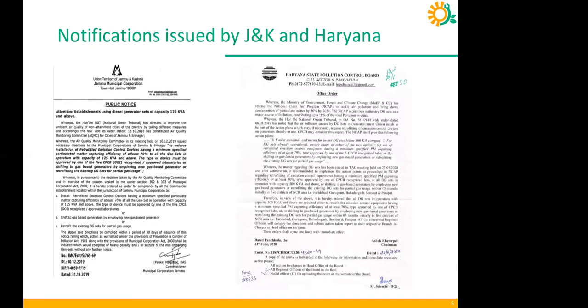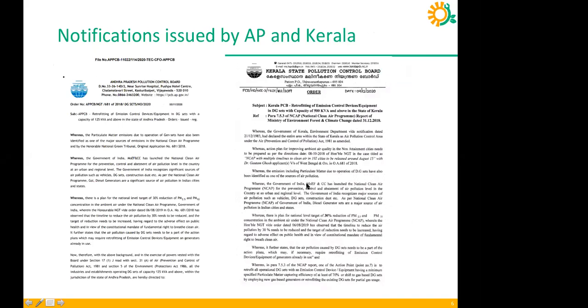Not only Tamil Nadu, we saw Jammu and Kashmir, Haryana, these two states also coming up with a similar kind of notification, wherein Jammu and Kashmir asked for capacity 125 kVA and above to be retrofitted. Haryana asked for 500 kVA and above to be retrofitted. Then we saw Andhra Pradesh and Kerala also bringing up such notifications. Andhra Pradesh also asked for 125 kVA and above, and Kerala asked for 500 kVA and above. Now we are also expecting Maharashtra, Uttarakhand, Karnataka to also come in line and bring such notifications, because the Honorable NGT, when it issued an order, directed it to all the states and union territories of India.